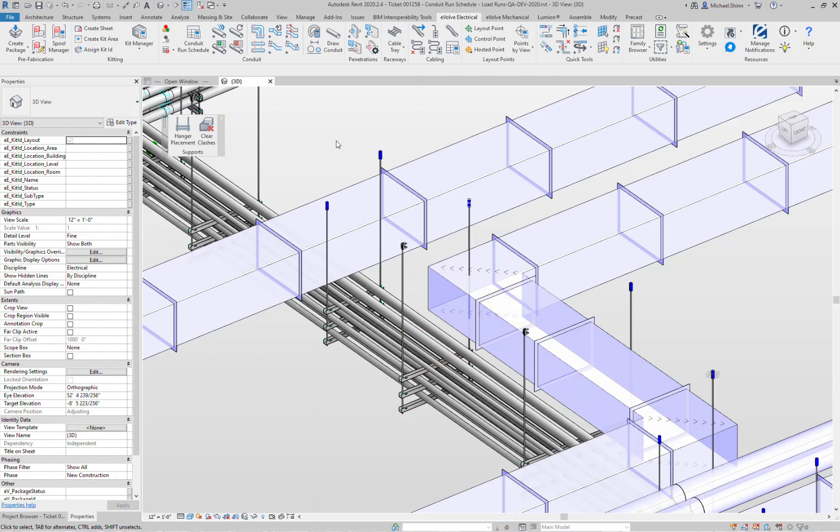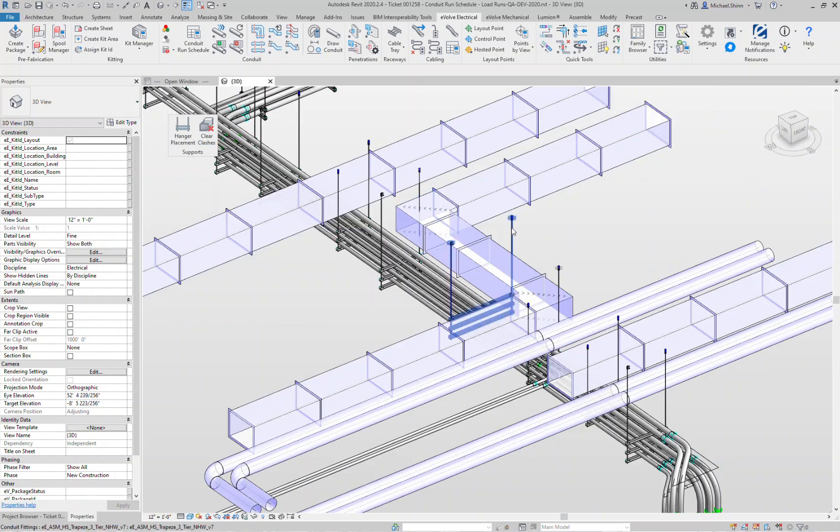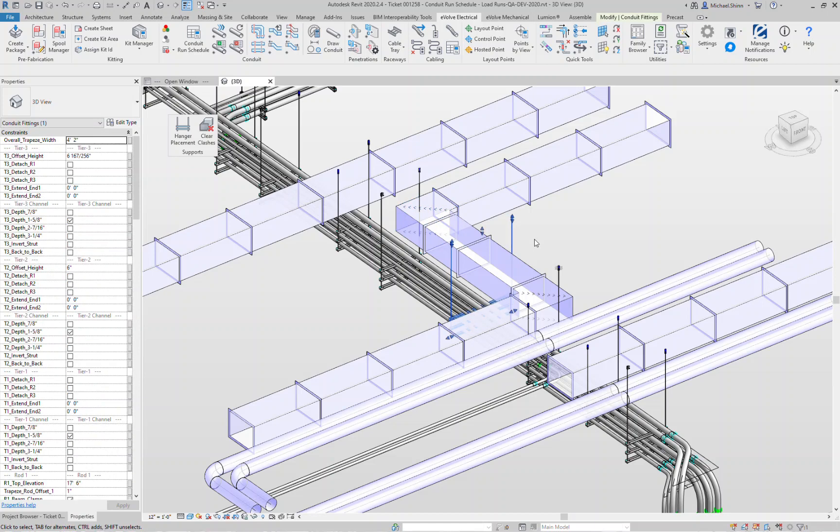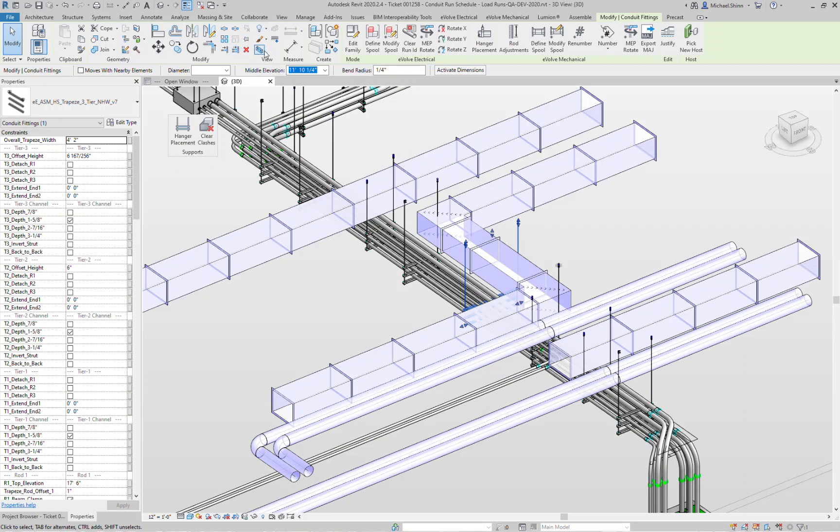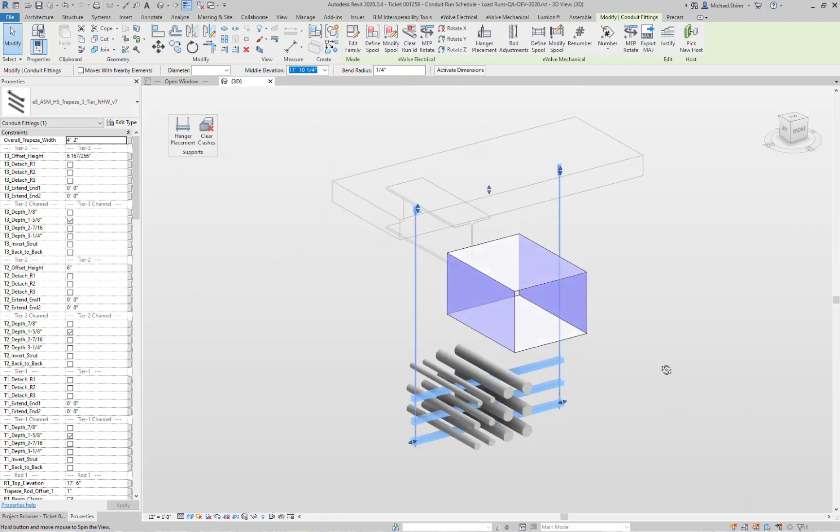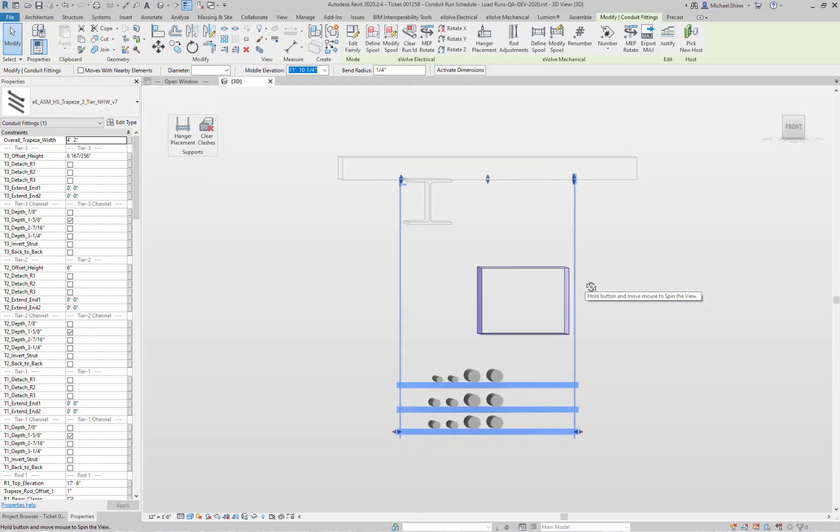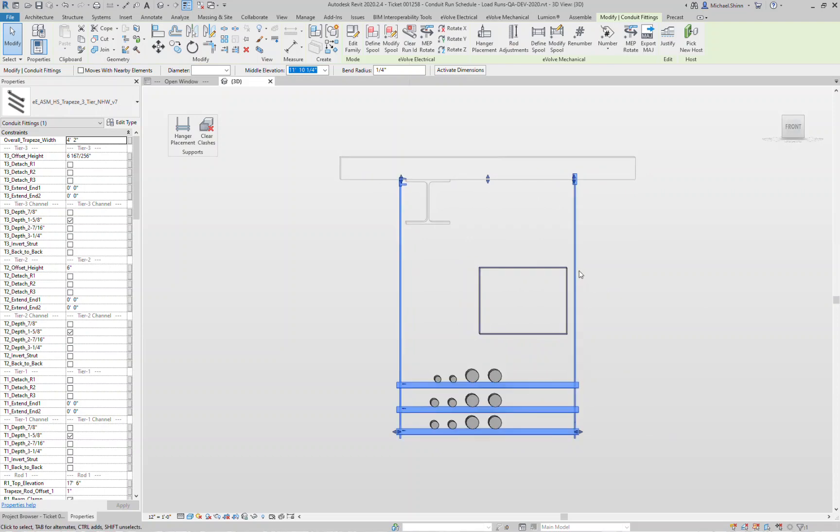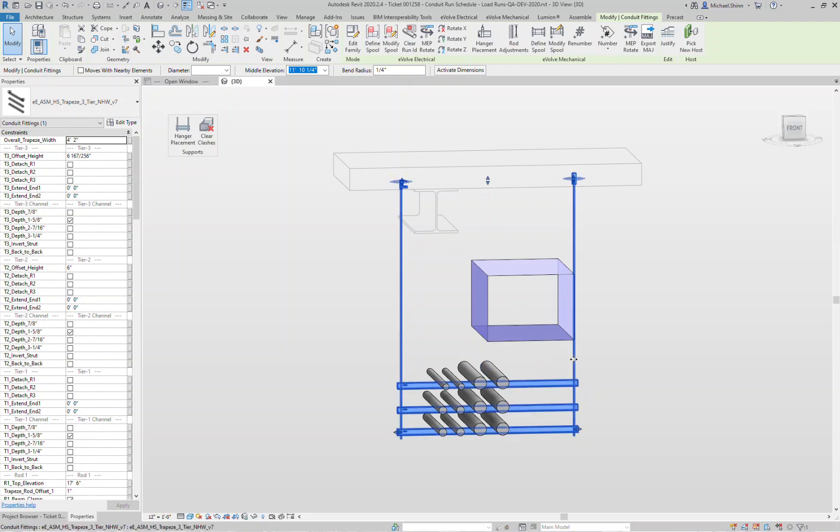As an example here, if I click onto this hanger, I'll show you the clash detection and avoidance edit that it's done for us automatically. We section box this little scenario here, so now I rotate this view. What it's done is done a lot of things here. One is avoided the duct work in this scenario, so it moved this rack all the way over following the stretching rules that are applied.